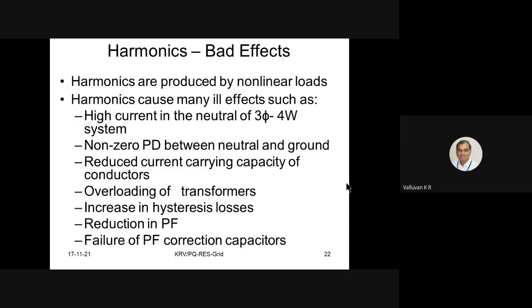Another effect is a non-zero potential difference between neutral and earth. Ideally, the potential difference between neutral and earth should be zero, but harmonics create a non-zero potential difference. Reduced current carrying capacity of the conductors, that is because of the skin effect. Overloading of the transformers: even though the load takes only X amperes of current, harmonics create 2X, 3X, etc. Increase in hysteresis losses: the magnetic circuits have more hysteresis loss when the harmonics are significant. Reduced PF: PF gets reduced because of harmonics. And if you install correction capacitors for improving the power factor, they fail because of harmonics. So problems are very many.